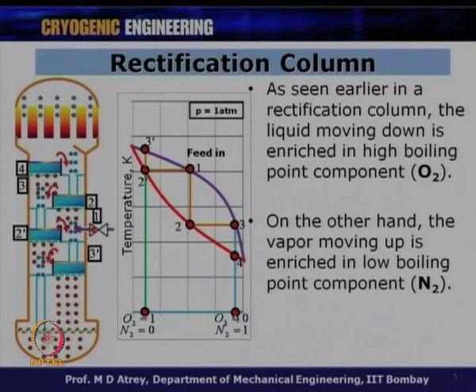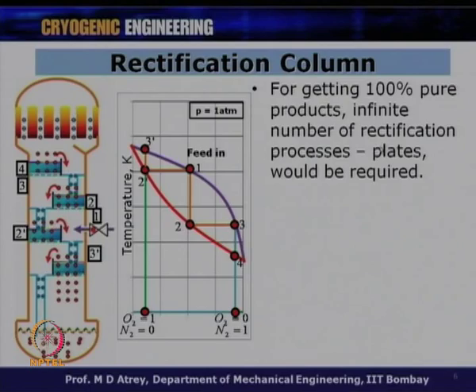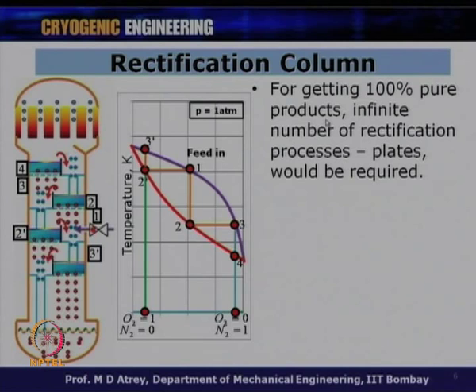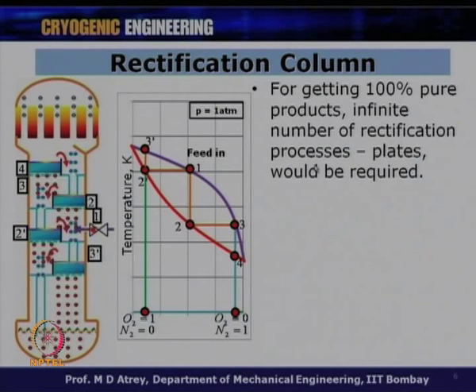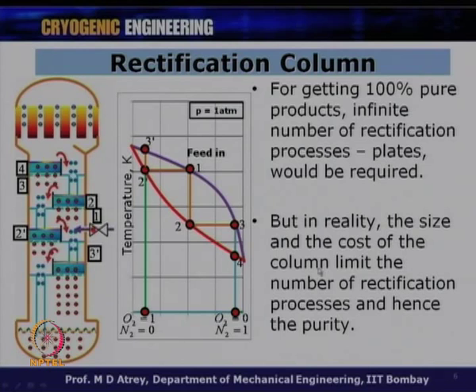This means that to get 100% pure products — whether 100% nitrogen or 100% oxygen — you would need an infinite number of rectification processes, meaning infinite plates, because heat transfer is never perfect and there will always be some ineffectiveness. In practice, the size and cost of the column limit the number of plates and therefore the purity achievable.